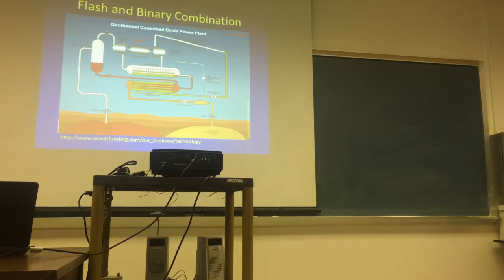For some plants, output is almost double in winter compared to summer, because of the efficiency of the condensers and the outside temperature. The motive fluid heats up, flashes to steam, goes through the turbine, then passes through the fans and condenses back to liquid. That's not very efficient in summer, but in winter it is, so their efficiency goes up a lot the colder it gets.